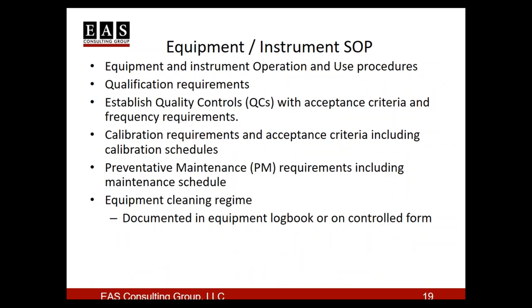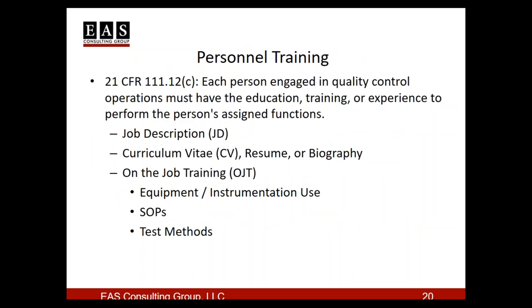There'll also be an SOP, which I alluded to earlier, that would describe the operation and use of the equipment. This would also have that qualification requirement like we just talked about. It would have what the QCs are, what the calibration requirements are and how often, what the PMs are, so what cleaning regimens and maintenance operations need to be undertaken. All of this will be documented in the equipment logbook or in a controlled form that would be put into a book. So there's a lot of work being done here on the equipment.